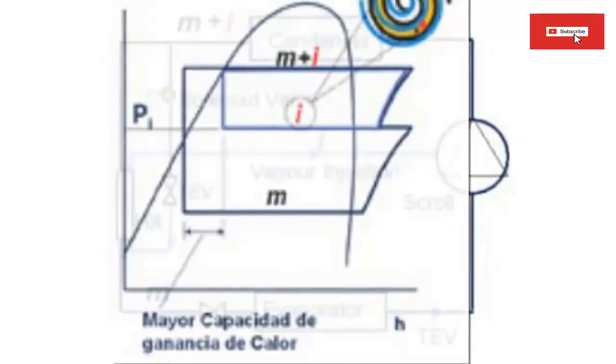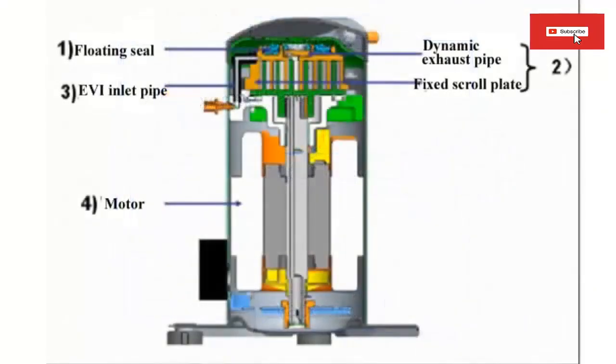10. The cycle efficiency of the scroll compressor with vapor injection is greater than that of a conventional single-stage scroll compressor, delivering the same capacity because the additional subcooling capacity is achieved with less energy.